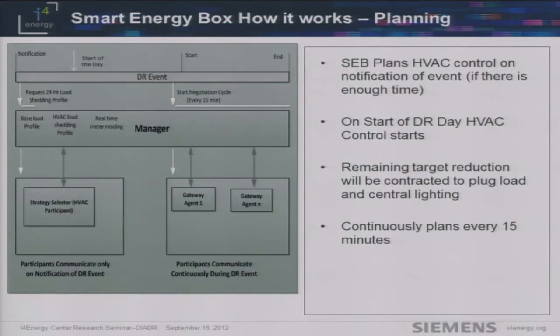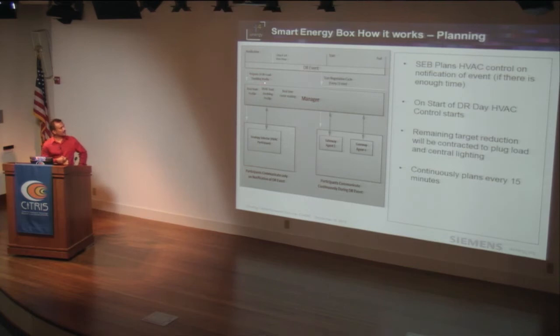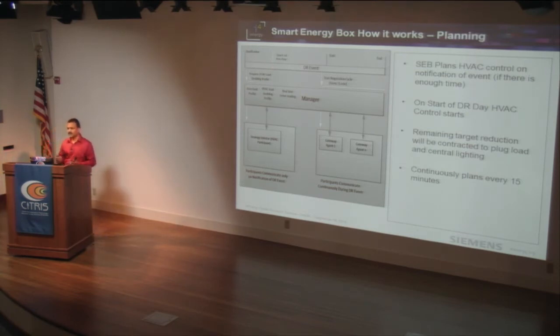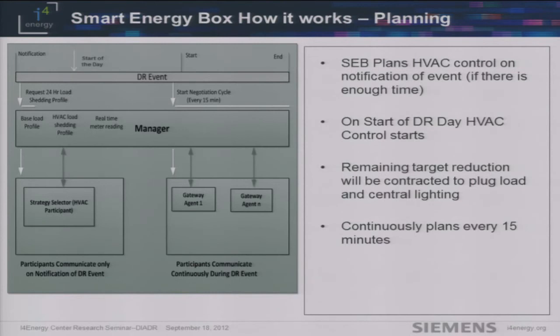This is how the Smart Energy Box works. Whenever a day-ahead event is notified, the manager inside the Smart Energy Box evaluates the available profiles using the strategy selector and brings in the right strategy for the next day. During the start of the day, it begins applying the strategy to the building. The strategy is a set of set points — in this building we control almost 450 control set points including thermostats, VAV flow, supply temperature, heating and cooling mode set points, as well as roughly 80 central lighting set points.